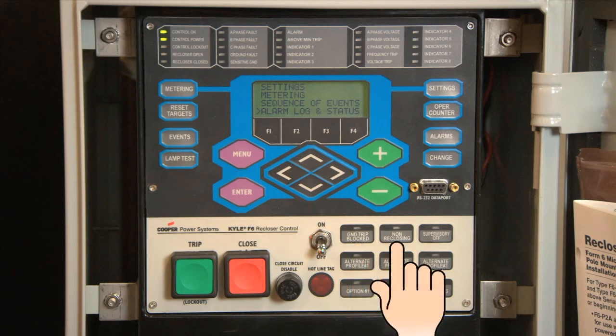Non-reclosing. The control is operating in a non-reclosing mode when the non-reclosing red indicator is illuminated. Non-reclosing mode disables any automatic reclosing operations. Non-reclosing does not alter the active TCC. Activation is possible from the serial port, input-output, the interface software, or locally.